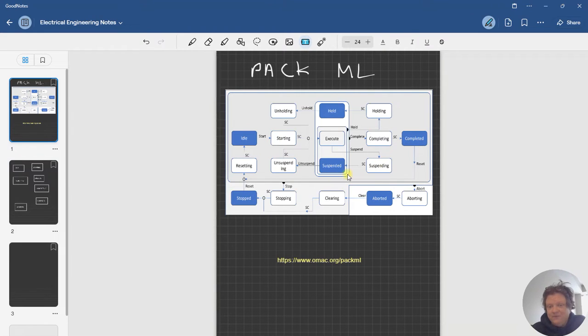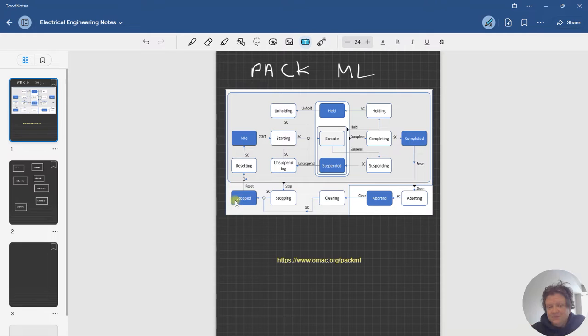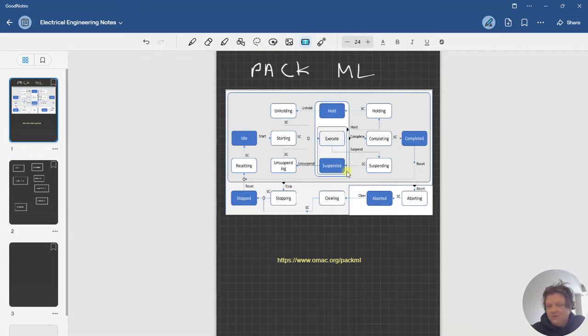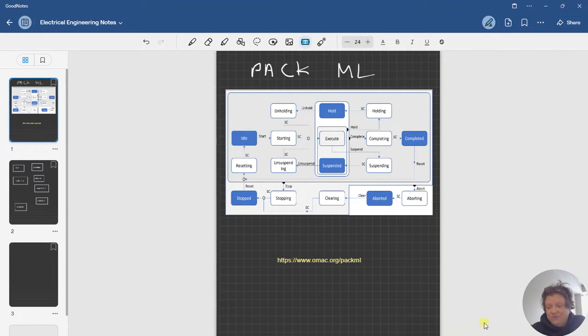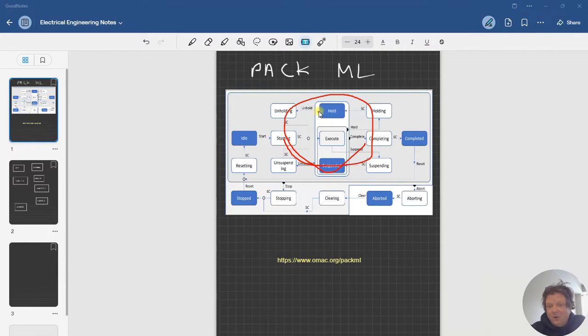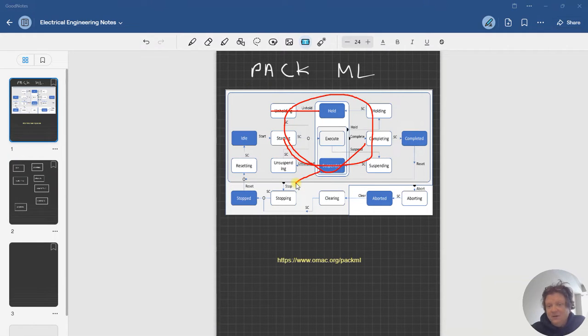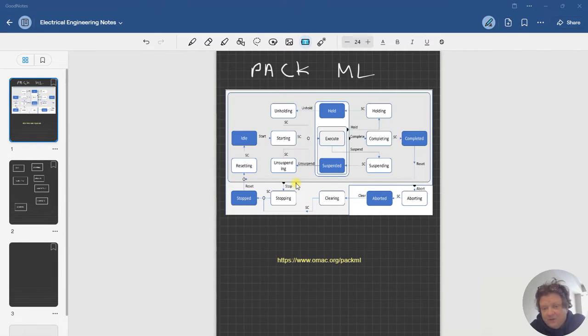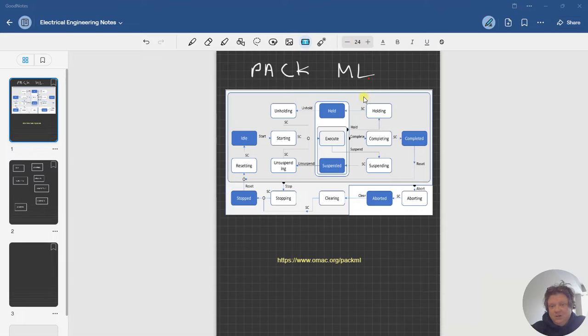we got stopped, idle, suspended, hold, completed and aborted. All of those are like in-between states for the basic stuff that we normally do which would be stop, start—they call it execute—and then when something is completed you go through the cycle again. When you're in the execution phase, you may have to hold or suspend. We're typically doing that right now with alarming or interlocks.